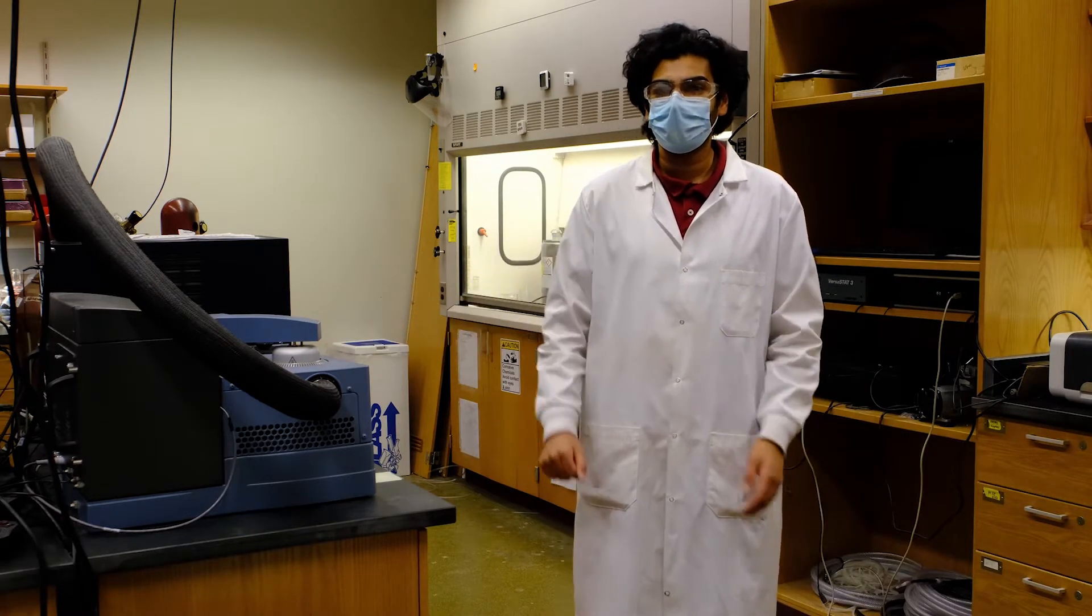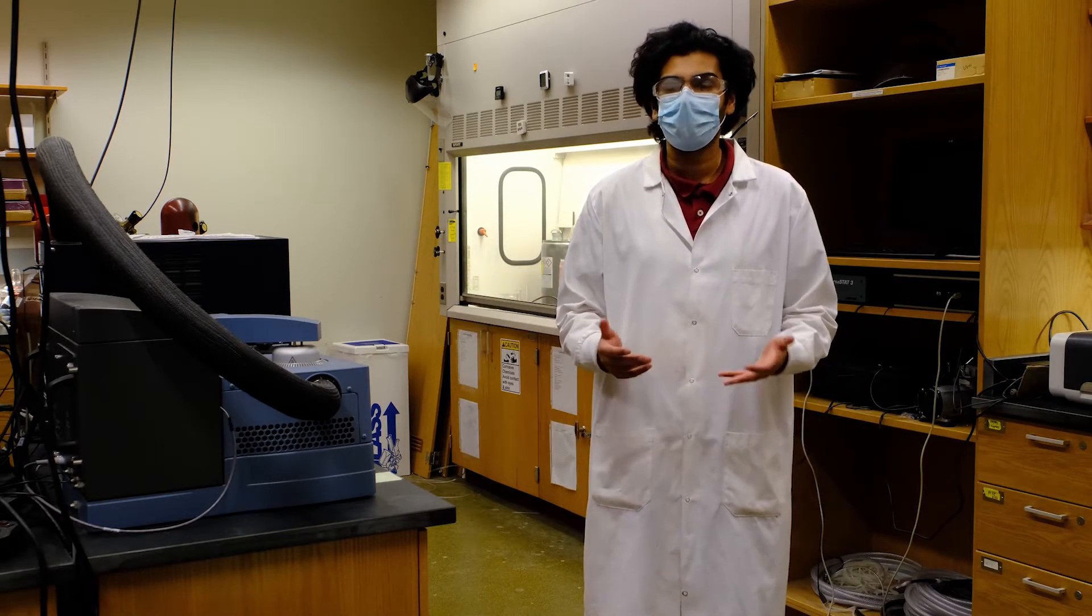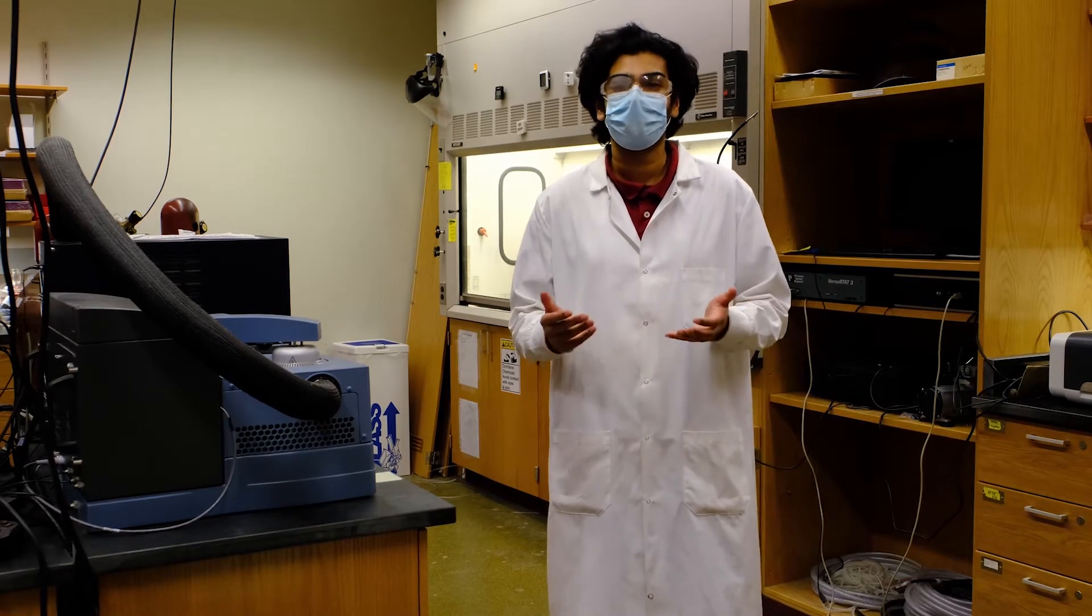This machine is a differential scanning calorimeter which we utilize to measure the thermal properties of polymers such as the glass transition temperature.